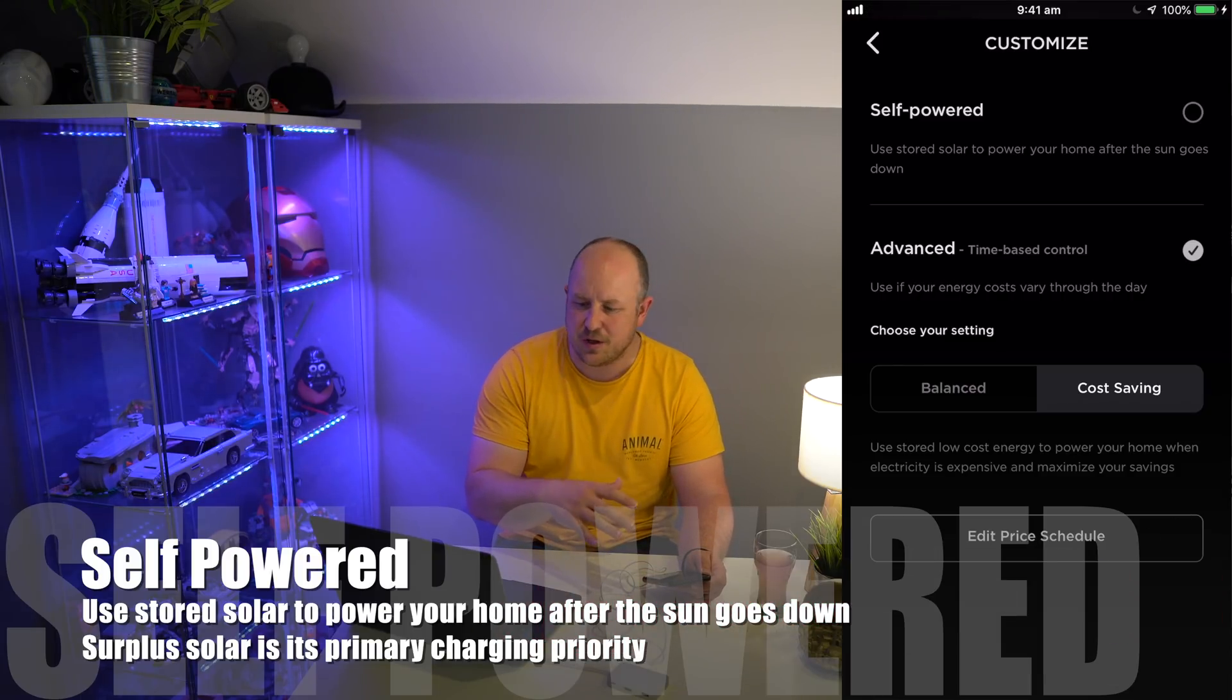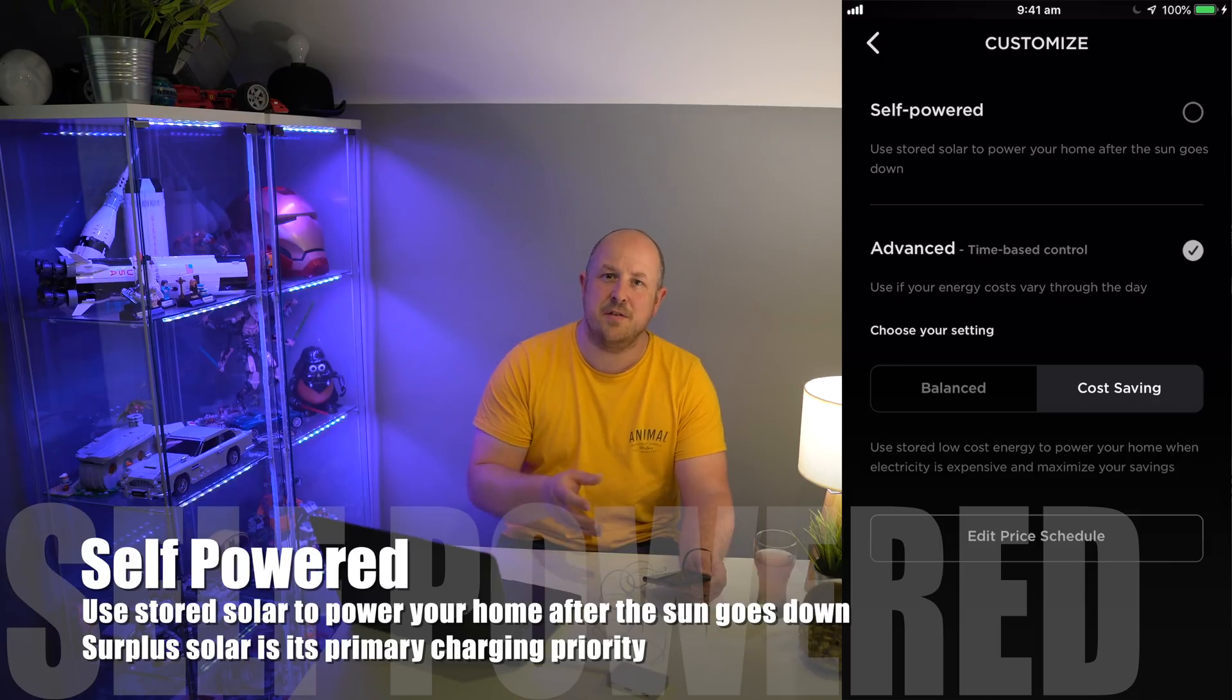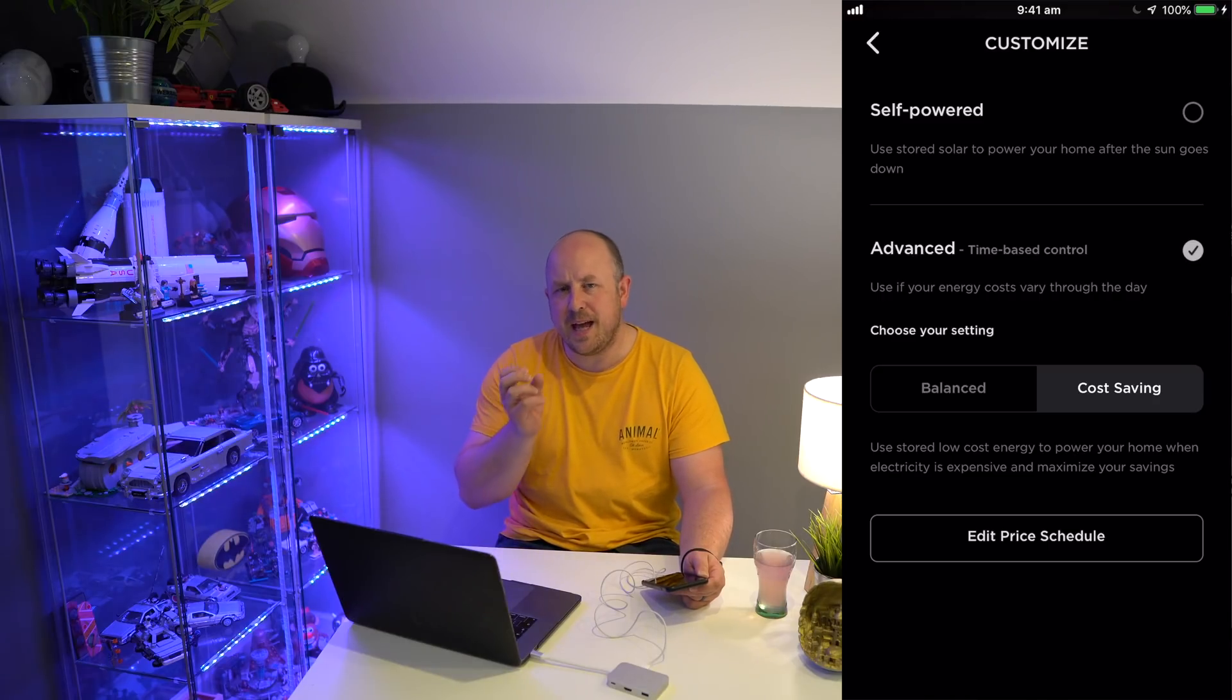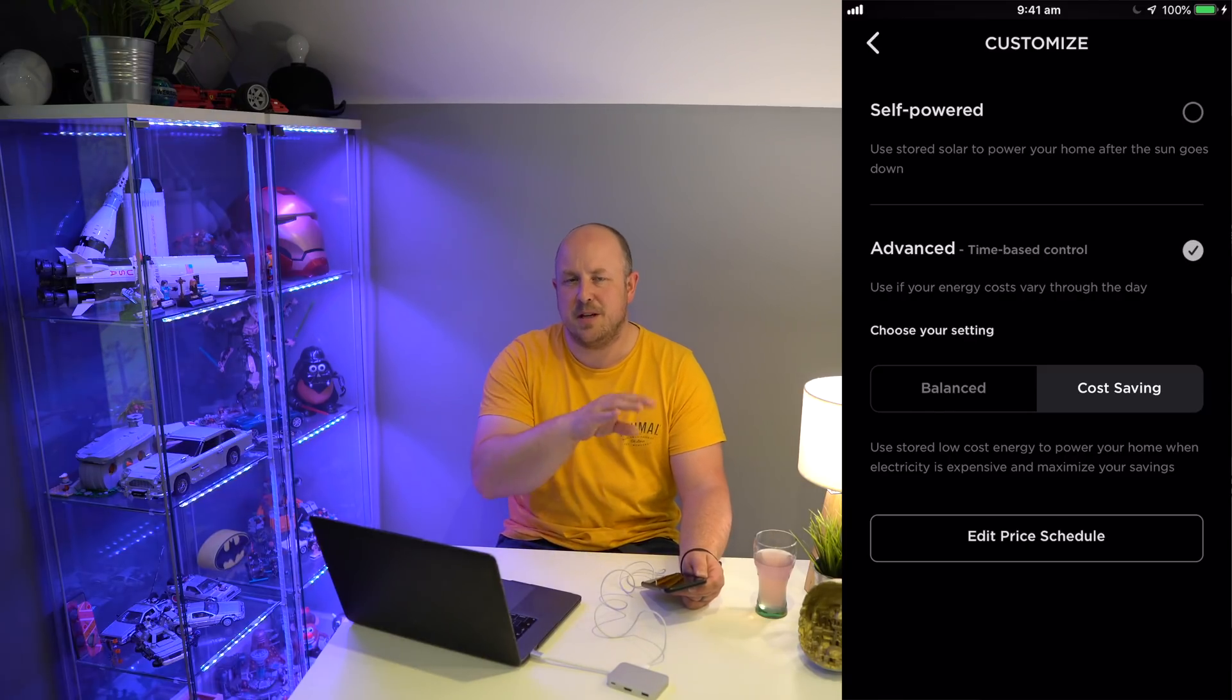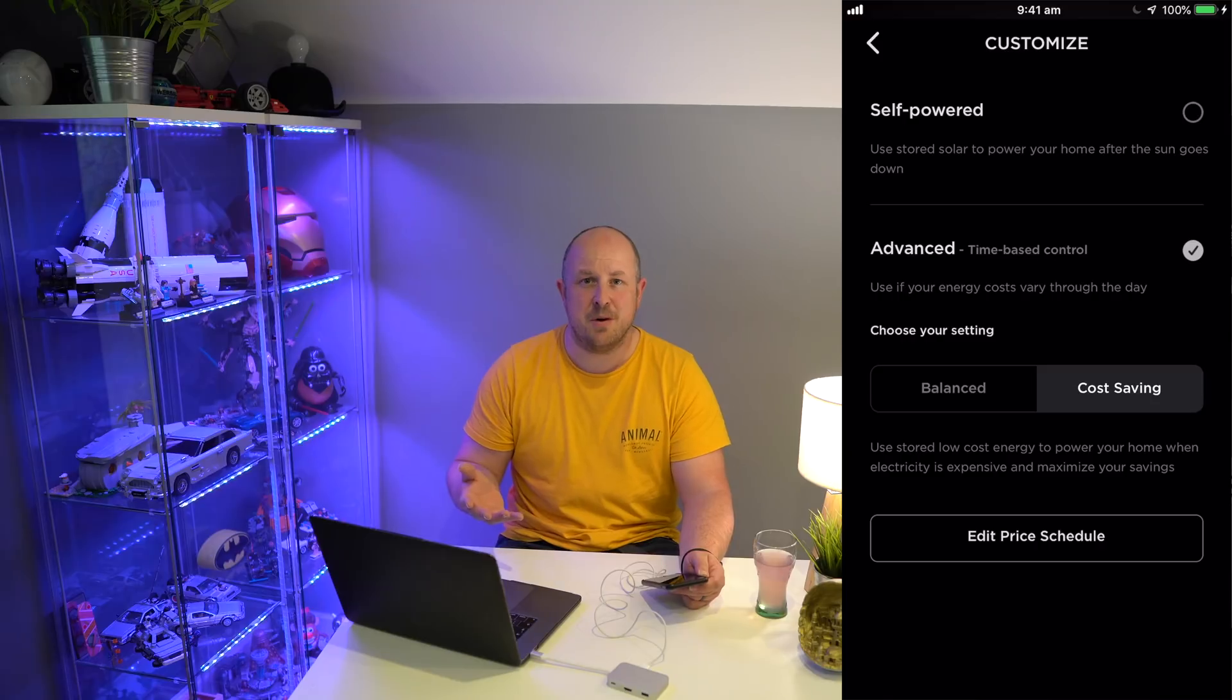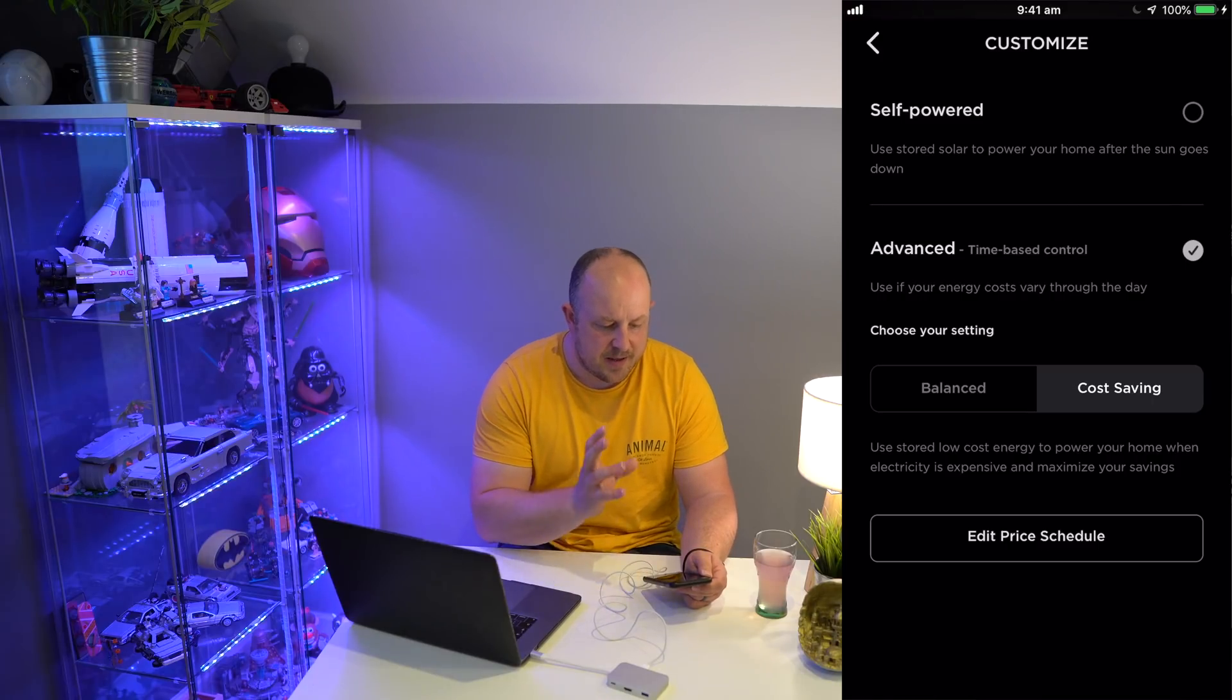Basically what this means is any energy you generate from your solar system will have priority to charge up the battery. When the sun goes down and your solar system is no longer providing sufficient power to your house, the Powerwall will take over that load and do that in partnership with the solar until all dependency on solar has gone. For example, if you're using one kilowatt of energy and your solar is generating 500 watts, the Powerwall will start to supply the other 500 watts, then slowly transfer fully over to your Powerwall.